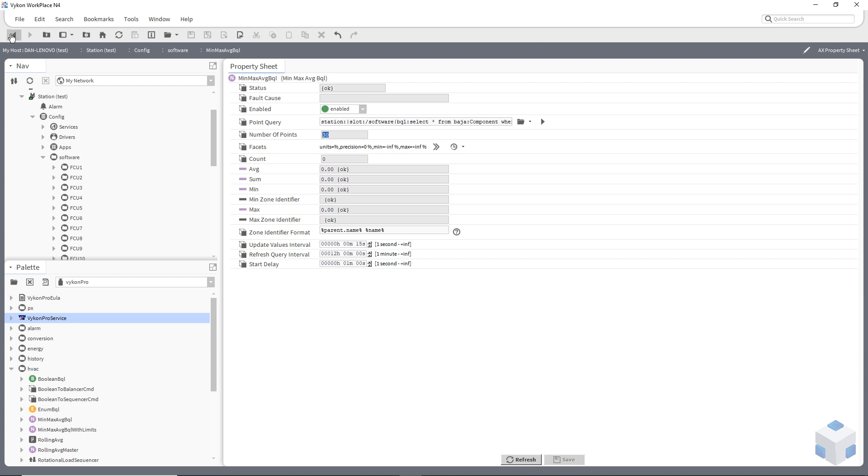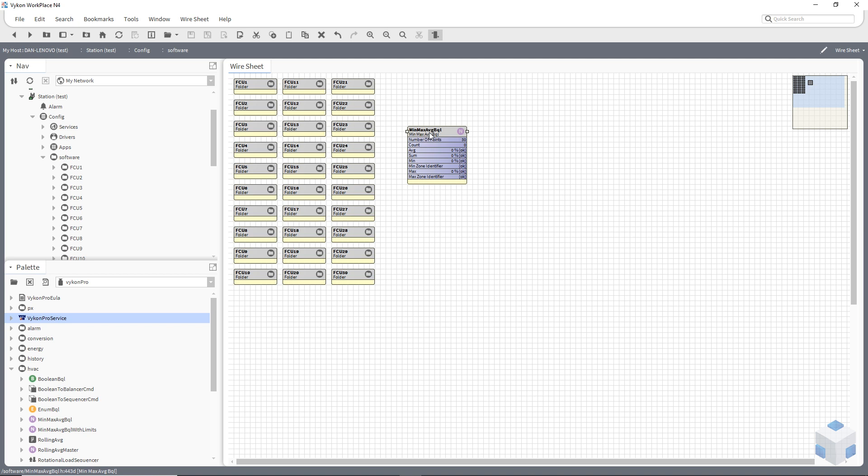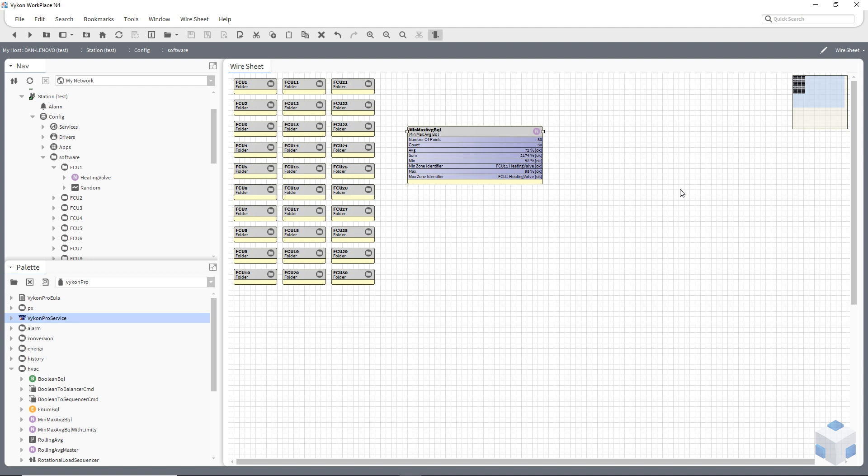So if I come back out and actually look at what's going on, currently I've asked this to look inside my software folder for a point called heating valve. I've asked it to actually identify it by using the parent name. And as you can see, it's now populated with data and this can update every minute, every 30 seconds, whatever you choose. So as you can see there, we've got an average of the floor, the summation, which probably not very helpful in this case, the minimum valve position, which is fan coil unit 11, and the maximum, which is fan coil unit 12.